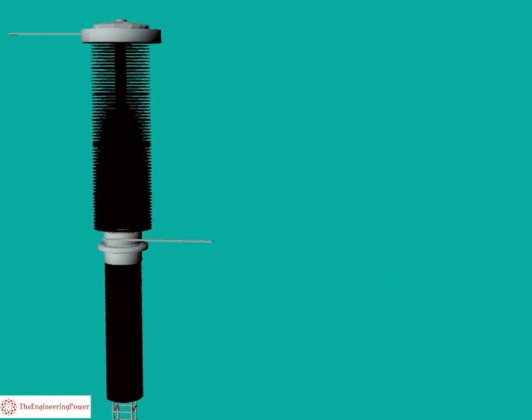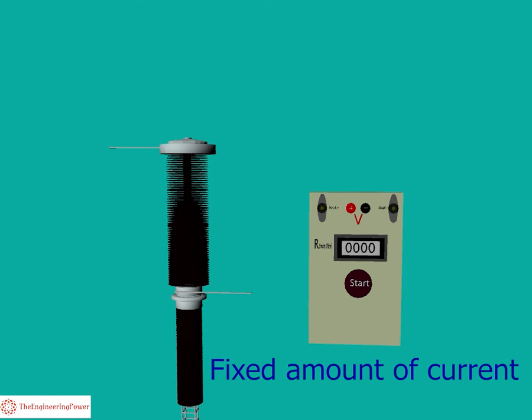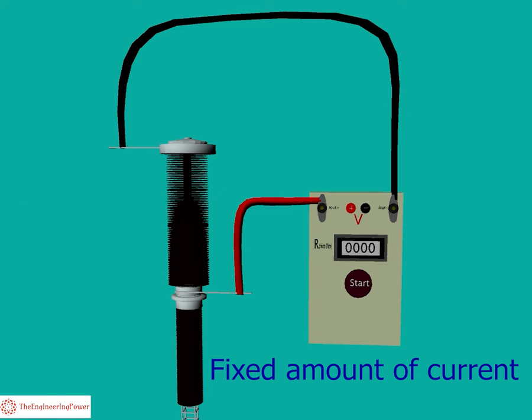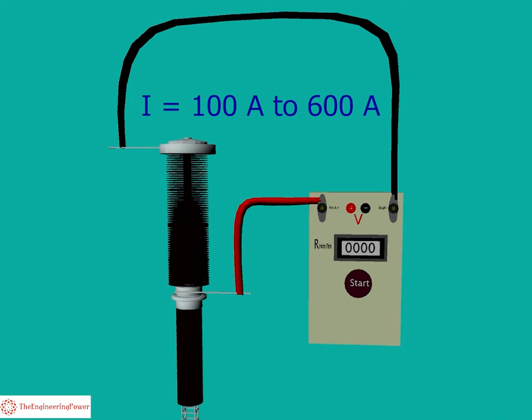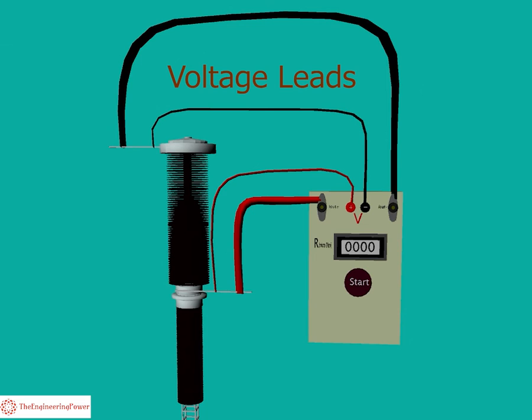In case of circuit breaker, first we make sure that the contacts of the circuit breaker are in closed position. A fixed amount of current is injected through the contacts of the circuit breaker using current leads of the testing instrument. The current value can be from 100A to 600A. The voltage drop across the contacts is measured using voltage leads of the test set.